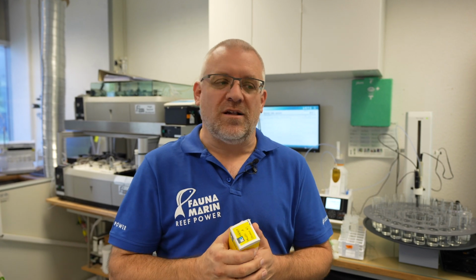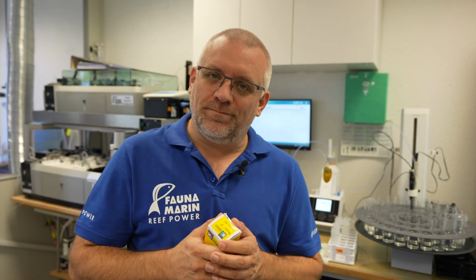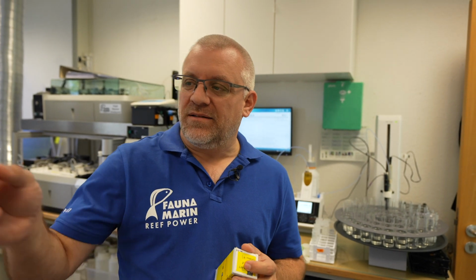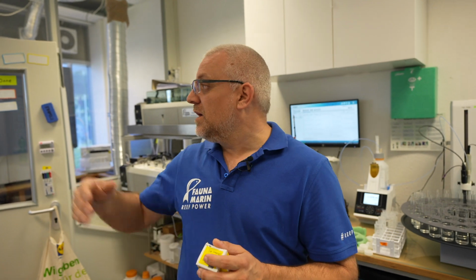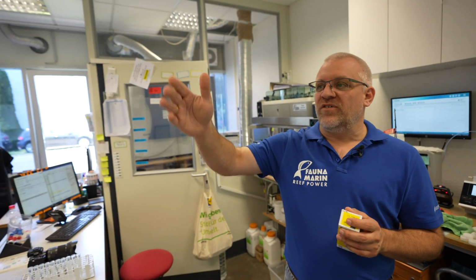Now, everybody will say, if you have a good calibration, you will have good results. The problem is, no. A lot of mistakes can happen inside a testing. Like I said, it could be a particle inside. It's possible that something sticks to the needle, which brings different results. If it's windy outside, that has an effect on the airflow to the machines. High temperature, low temperature. Even the person who works on it can produce different results.